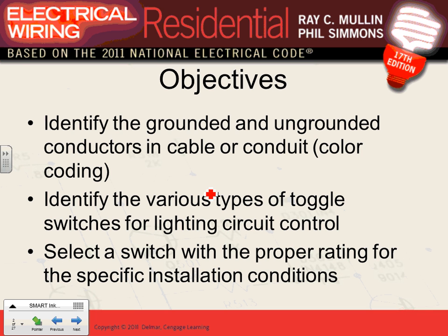As I said, this is mostly for project managers, because you're going to be auditing your own jobs before you leave. We love the grounds in the US, and we define all the conductors based on the ground. We have the ungrounded conductor, the grounded conductor, and the grounding conductor. The problem is, when we inhabit the moon or Mars, how are you going to call these conductors? You can't put a conductor on the moon and call it a grounded conductor. Ground is Earth, unless you redefine the ground as the moon. Anyway, everything is defined by the ground here: grounded, ungrounded, and grounding. Everybody knows ungrounded is the phases, grounded is the neutral, and grounding is the ground. These are very big terminology that we use.